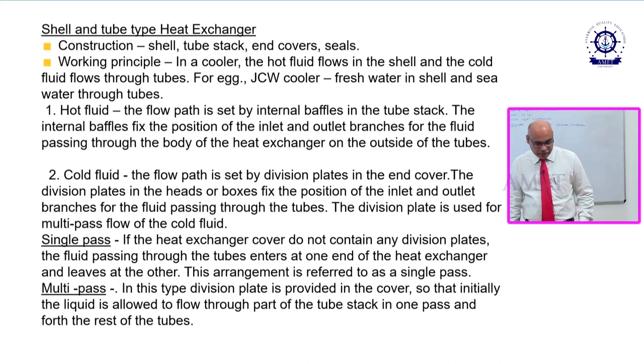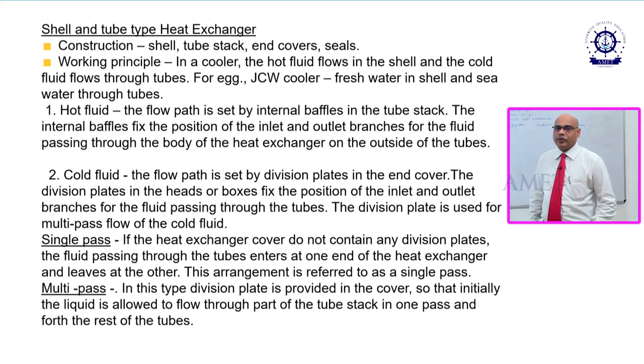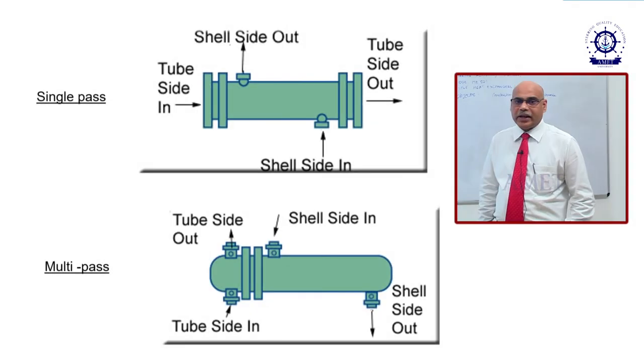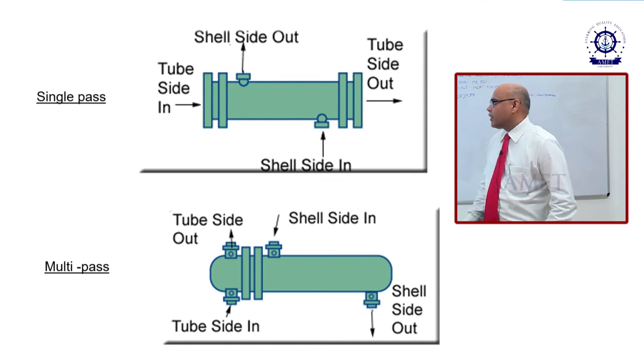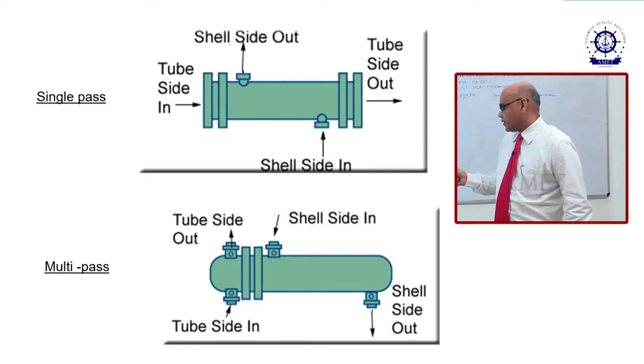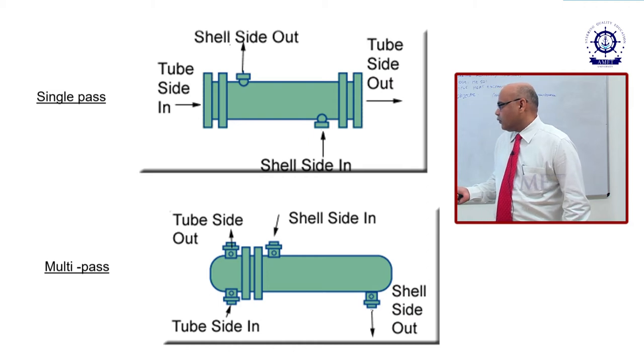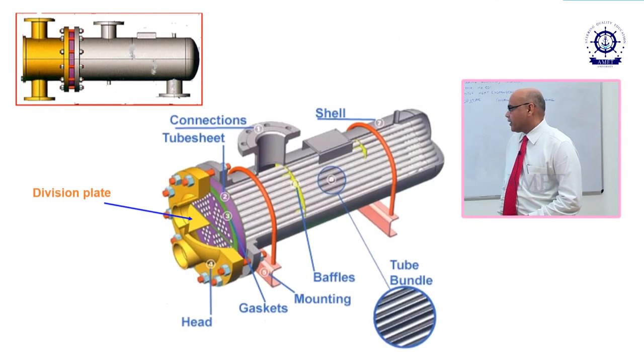What is the working principle? Generally, the hot fluid flows through the shell and the cold fluid flows through the tubes. There is single pass and multi-pass. In single pass, the fluid flows through the tubes and straight away comes out. In multi-pass, the fluid enters one side, takes a U-turn, and comes out the other side via a division plate.